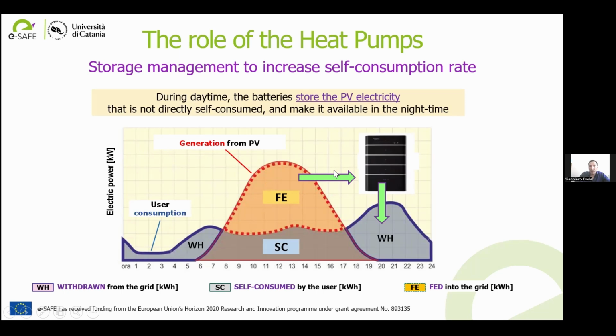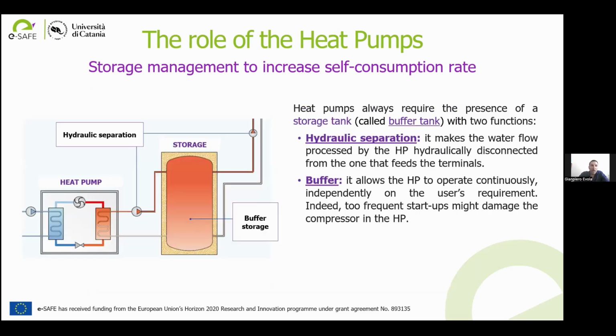So the systems we are talking about need to maximize the storage capacity in order to maximize cost effectiveness and self-consumption rate. But in order to maximize the storage capacity, we can of course rely on electricity and on batteries, but we can also rely on thermal storage. So heat pumps can heat the water, even if in that moment there is no requirement of thermal energy by the user. Water is stored inside a tank, and then the users will draw water when needed. We have a decoupling between production and storage, and this can also maximize the cost effectiveness if we let the heat pump work when there is PV electricity available.